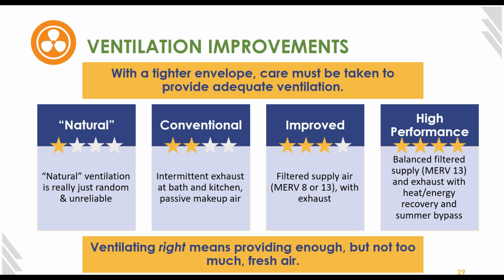So an improved ventilation approach to this exhaust only with passive makeup air would be to actually provide filtered supply air. So filtered at MERV 8 or MERV 13 levels, in addition to exhaust air. So you're providing filtered fresh air and you're exhausting air from those areas like the kitchen and the bathroom that can have a lot of moisture buildup. And so this provides a more balanced ventilation approach, and you know where your supply air is coming from.